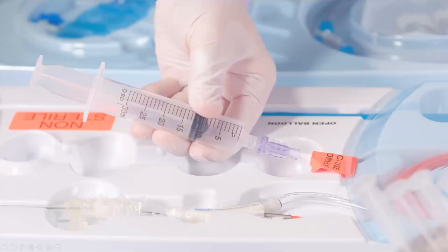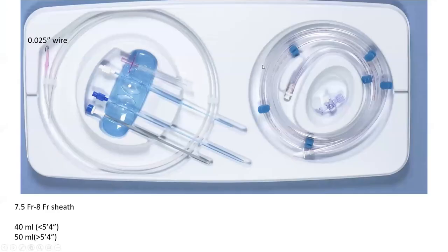Okay, but so you put negative suction on this, and you flush the arterial lumen. That's one thing. The second thing is the second tray. The second tray has the extension tubing for the helium line, which you connect eventually once you're in the body, ready to augment. And you have extension tubing for the arterial line, usually 40-inch line tubing, which you flush, okay? You flush that line. And you remove this from the tray and you make it ready for eventual connections.